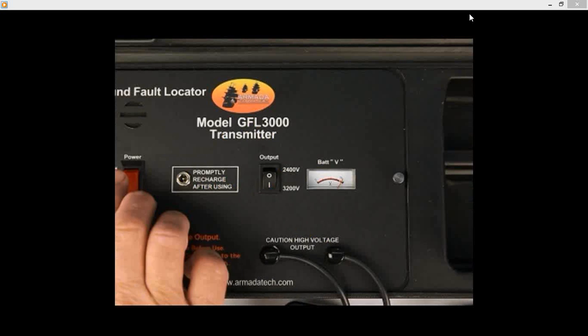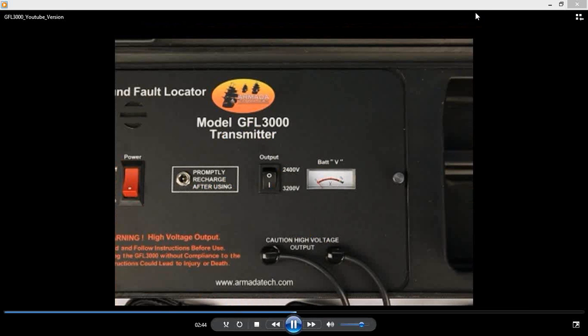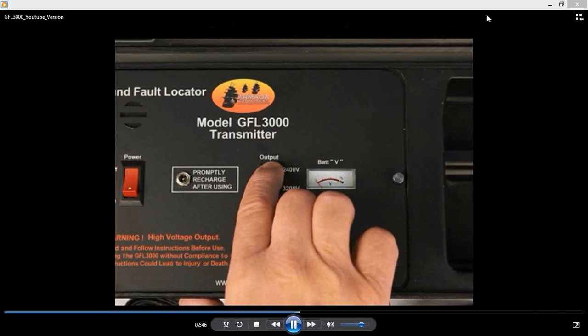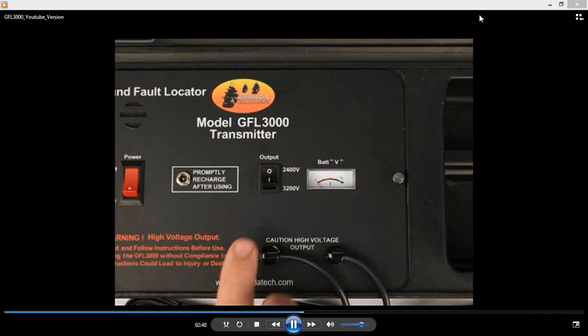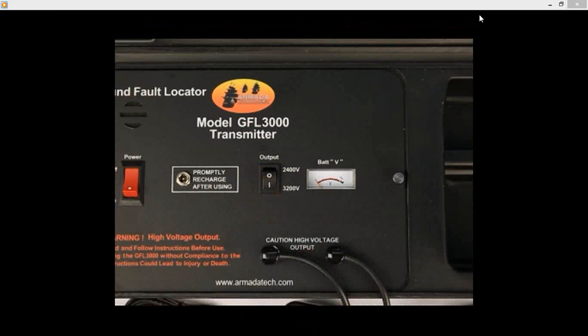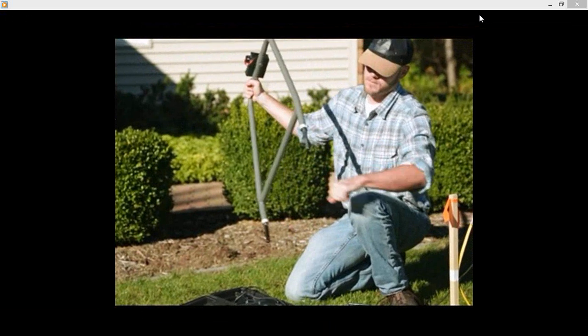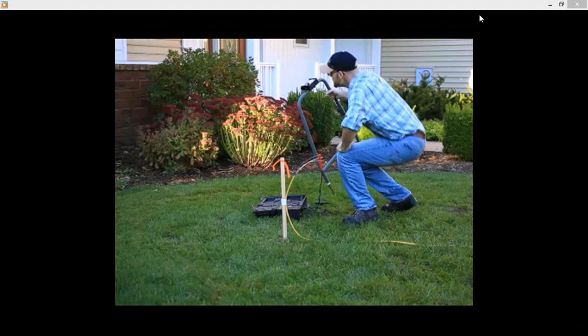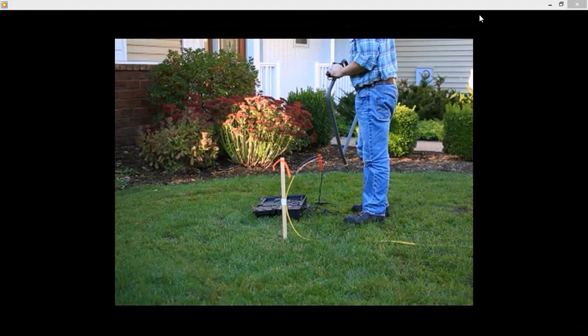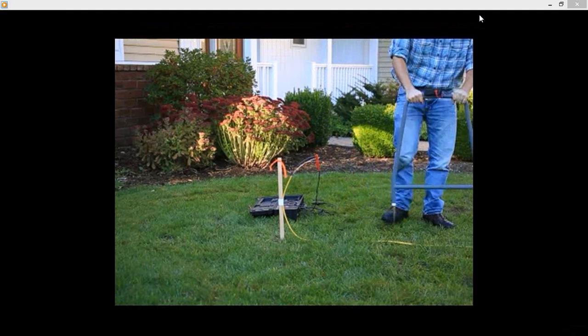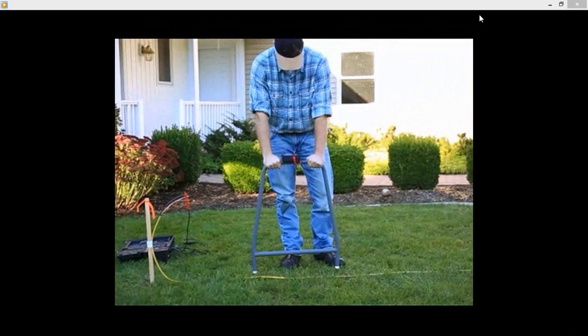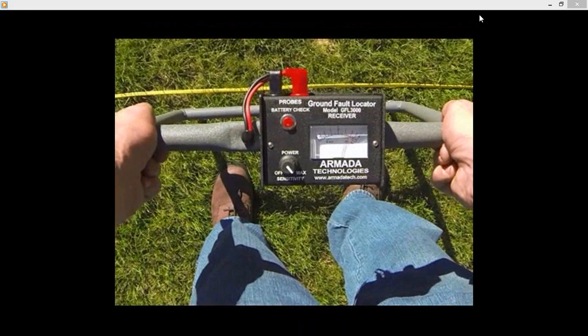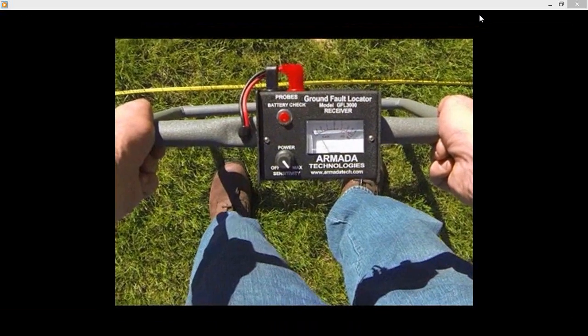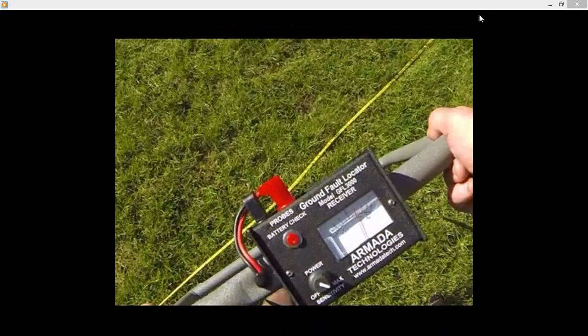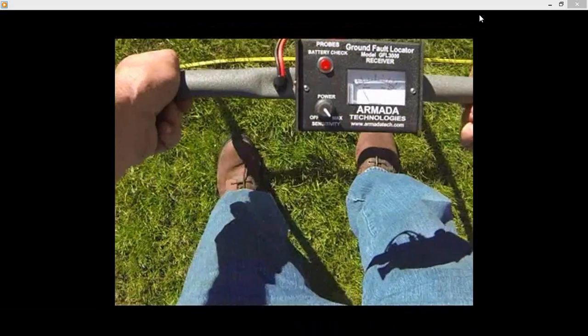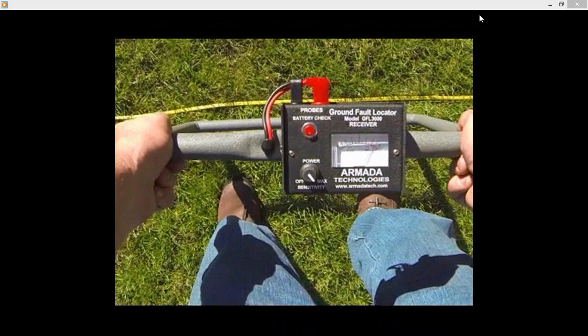Select low or high power as per your preference. High power will find all leaks, large or small. Low power will concentrate on larger faults. Remove the black insulating covers on the probes of the receiver. Turn the receiver on and place the receiver probes into the ground along the path of the cable. As the transmitter pulses the current, you should see the needle on the receiver kick in the direction of the fault. Watch for the direction of the initial kick of the needle and disregard the rebound kick.